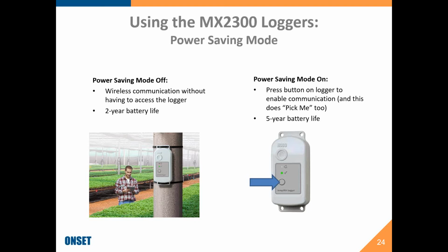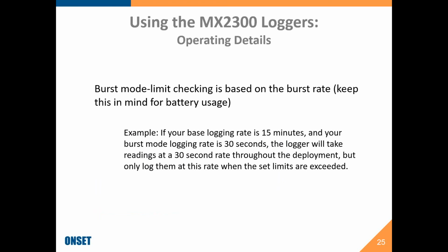But right now, you have to be out there with your mobile device to push the buttons in the mobile software, the HOBO mobile software, to do the readout, get the readings, and upload the data. So once you have the data on your mobile device, it can be automatically uploaded to the internet, but it still requires somebody to go out there in the field. Now, one of the things to keep in mind is if you can't make it out there, because this is a free app, you can have somebody else download the free app and go out and offload the data on your behalf, and then share that data with you. So that's an option to keep in mind. Thanks for those questions. I think it's good to address those.